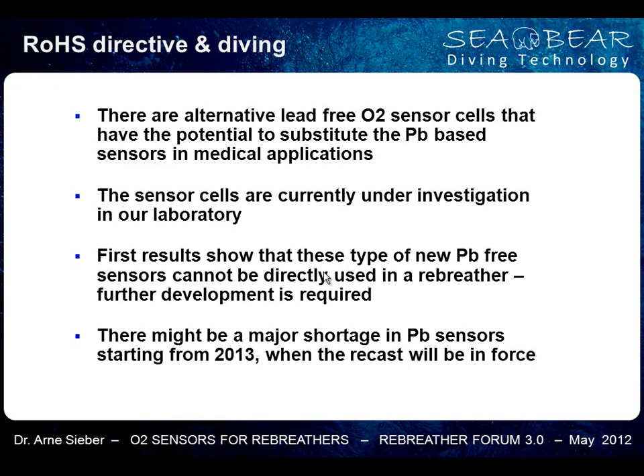So, there are alternative lead-free oxygen sensors. We are currently testing them. They work quite well, but we have seen that there is some hysteresis in the sensor signal. So the sensors work well in the medical field if you stay at 1 ambient pressure, but as soon as you change the ambient pressure, you get a hysteresis, so it needs some more development. If you want to use this in a rebreather, you need further development. But the problem is that the medical industry is big in comparison to the rebreather market, and if this recast directive gets into force, and these type of sensors will be banned, there are no oxygen sensors for us.